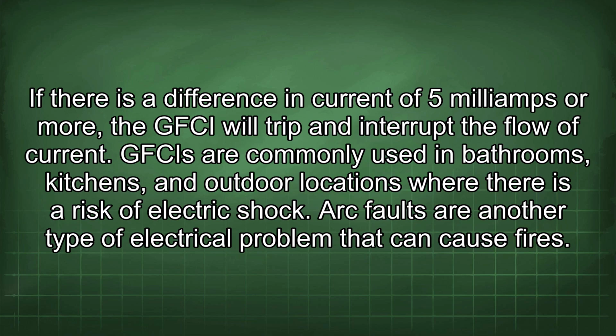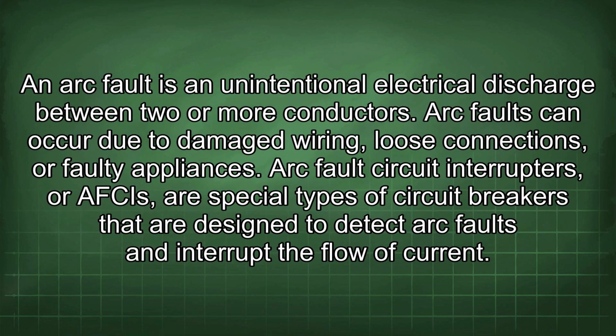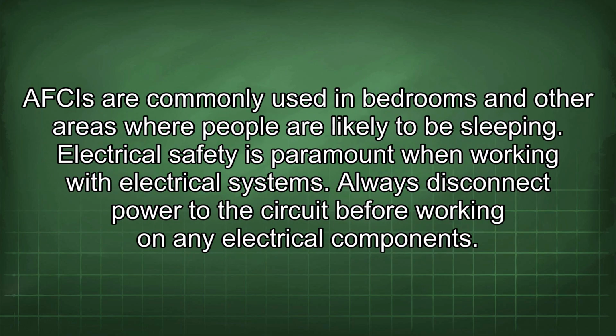Arc faults are another type of electrical problem that can cause fires. An arc fault is an unintentional electrical discharge between two or more conductors. Arc faults can occur due to damaged wiring, loose connections, or faulty appliances. Arc fault circuit interrupters, or AFCIs, are special types of circuit breakers that are designed to detect arc faults and interrupt the flow of current. AFCIs are commonly used in bedrooms and other areas where people are likely to be sleeping.